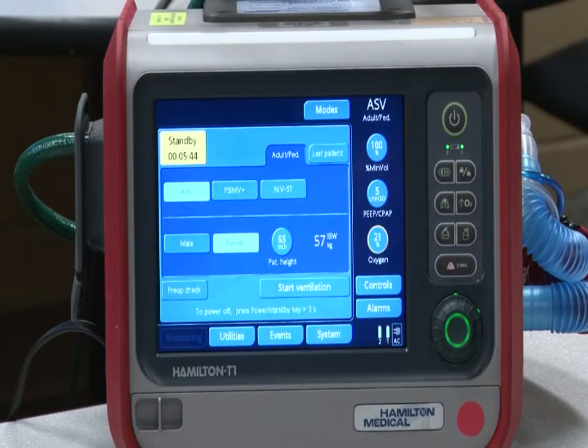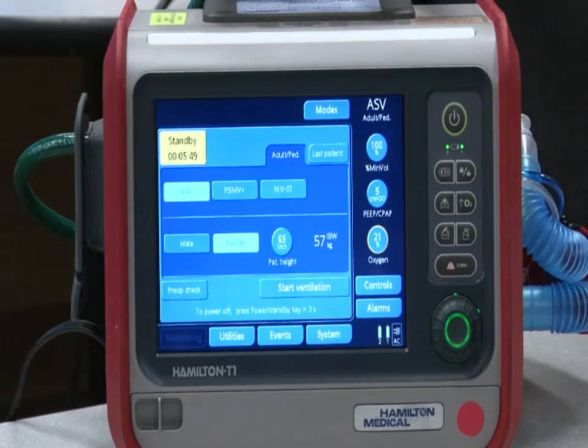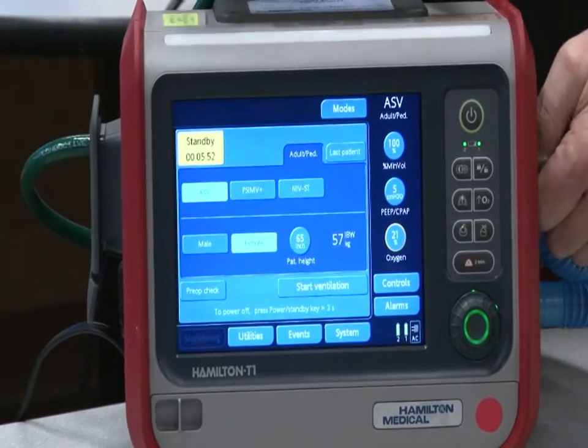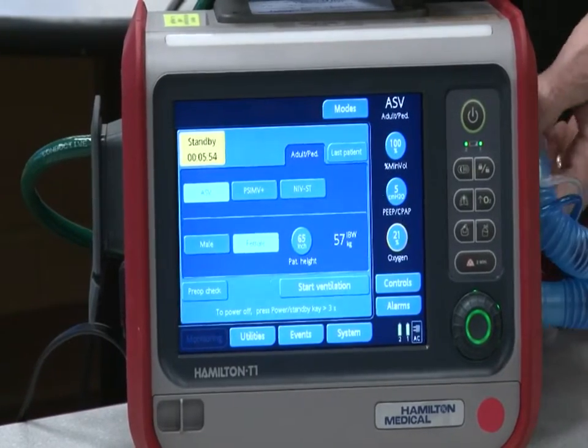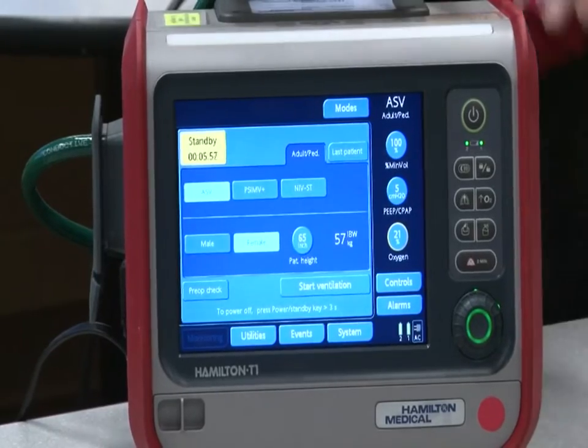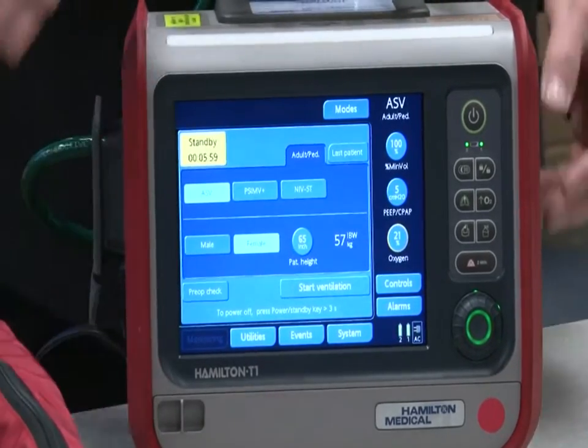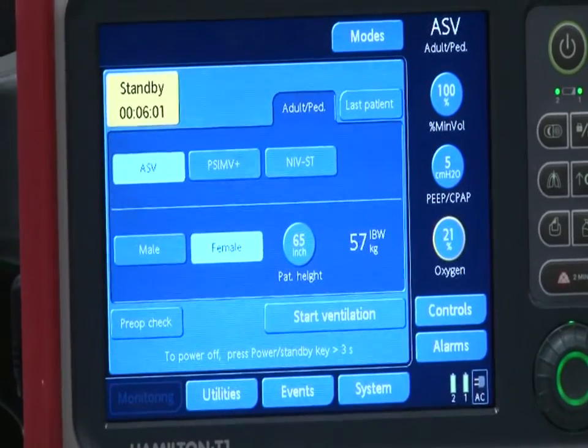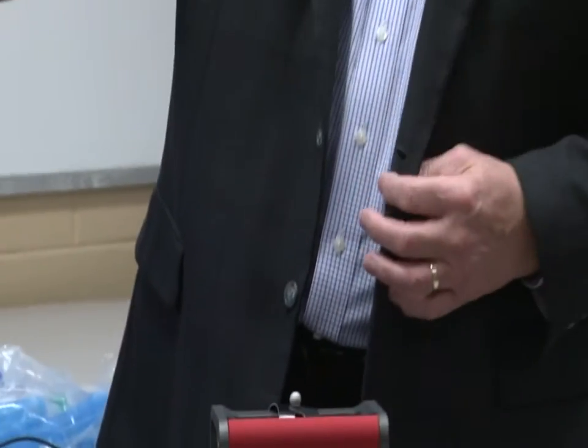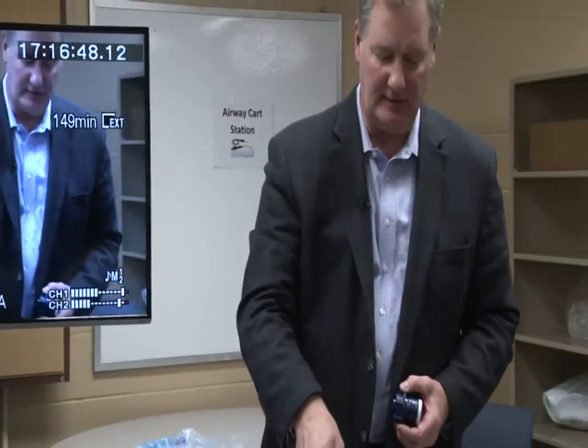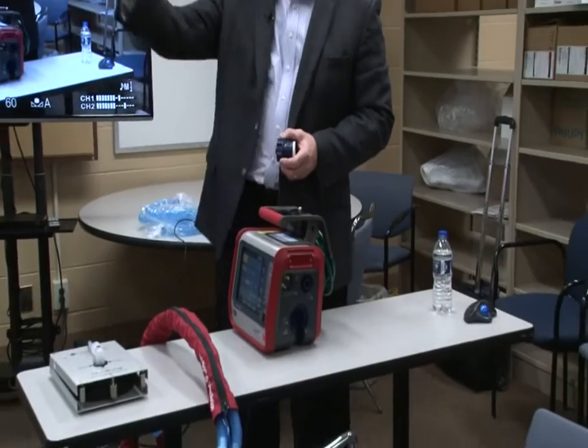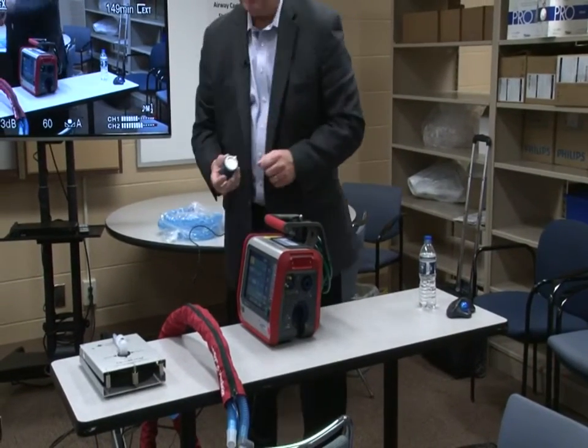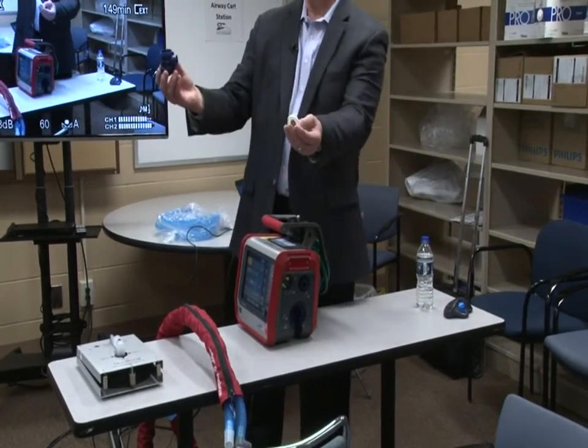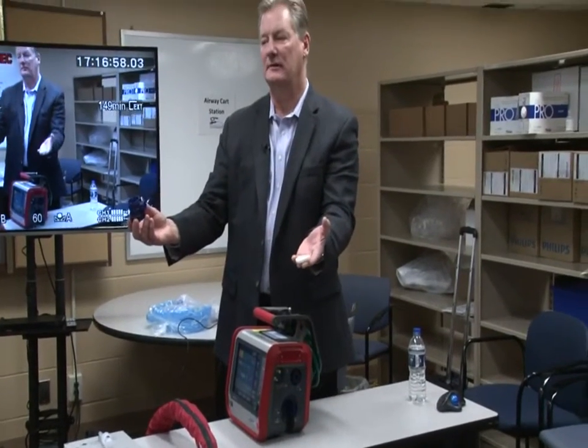Okay, so now we're going to do a couple of things that we would do before we use the ventilator, and that would probably be even before we did what we just did. Your ventilators don't have circuits on them yet, and let's not put those on just yet. One of the things that needs attention is called the expiratory valve. So if you go ahead and turn the ventilator so you can see the expiratory valve, with the screen facing to the left, it comes out, and there's also a membrane on it, and you can take that off as well.